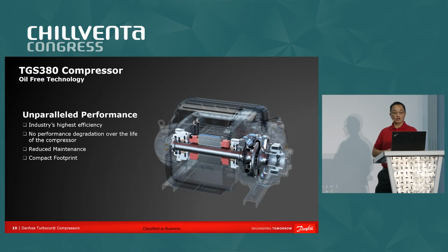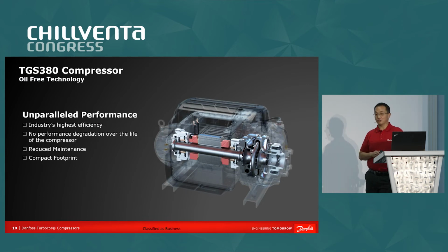As with all Turbocor compressors, we use oil-free compressor technology. There are two stages of centrifugal compression and oil-free magnetic bearings. That technology offers very significant benefits to the customer. No metal-to-metal contact, therefore no mechanical wear over time, and so you get consistent performance over the life of the compressor. In addition, you get much higher reliability and better efficiency, because you do not have oil to contaminate the system, as well as oil that could degrade performance over time.